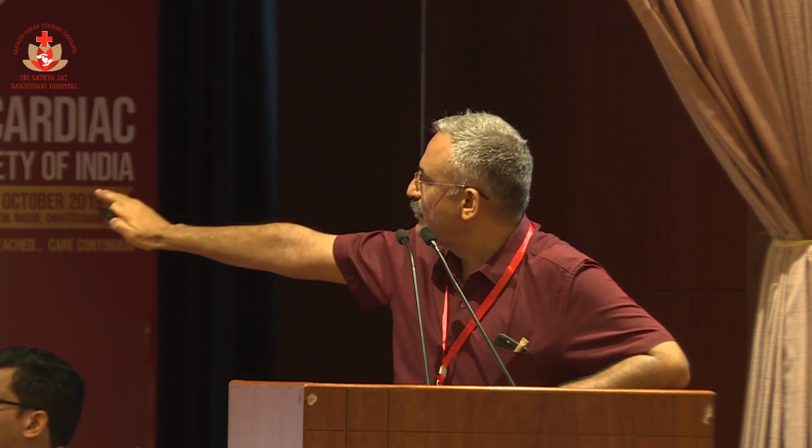And this is just an example from a surgical field. You can easily make out the new cannulas and the old cannulas. And many of our surgical friends will probably agree with me. The aortic cannula is tied practically at the same point all the time to secure it's not moving in and out. And it definitely starts weakening. The wire reinforcement starts weakening. And there will be an accident waiting for you one fine day. And I don't know how many times the cannula has come back. I've never gone to check how many times this cannula has been reused.